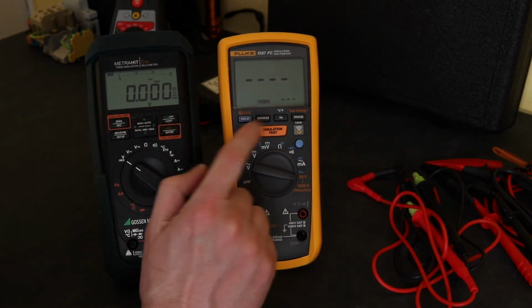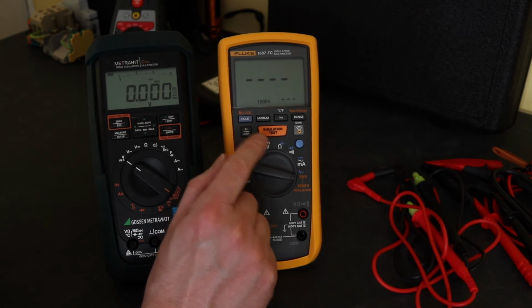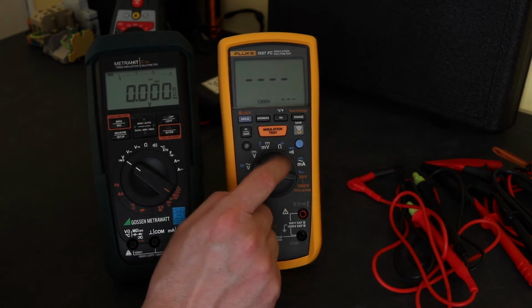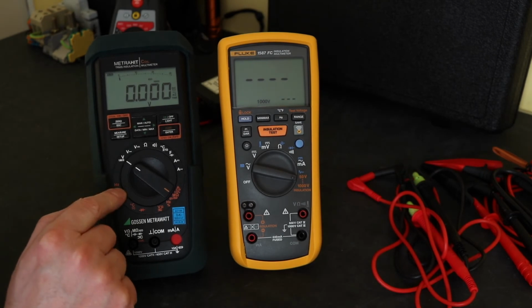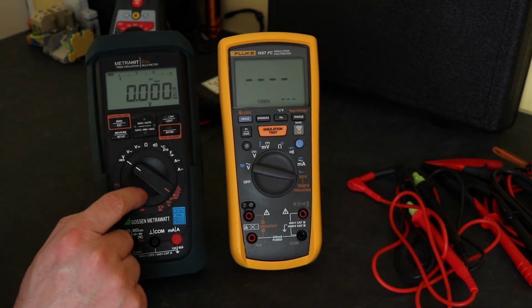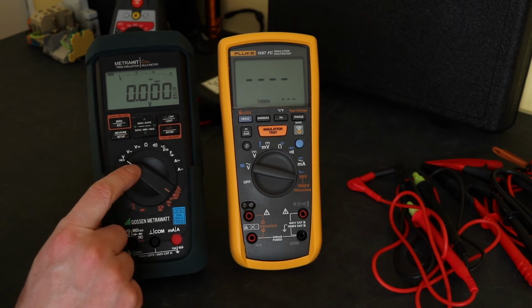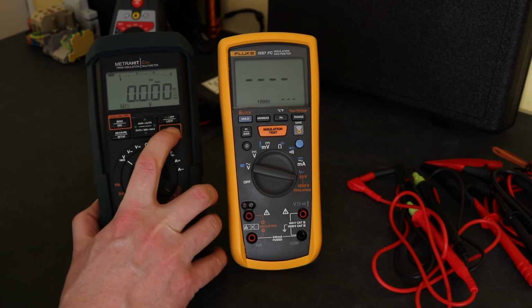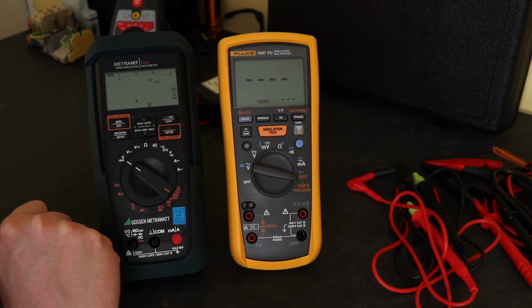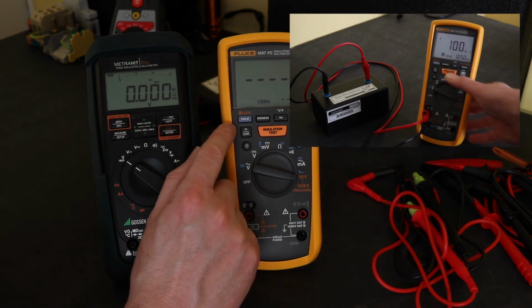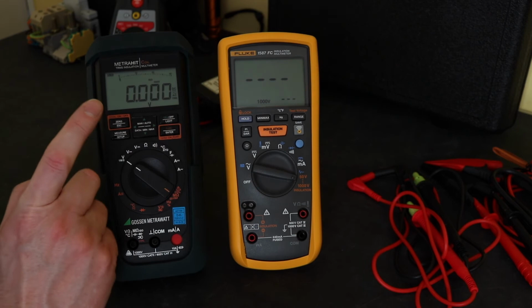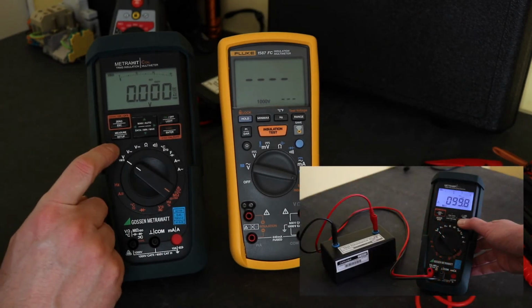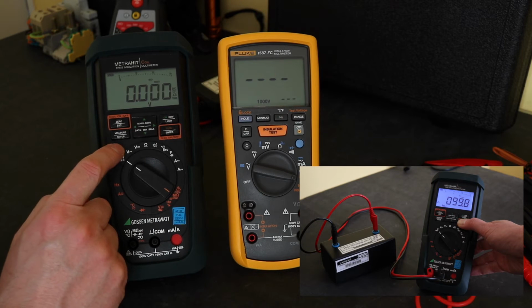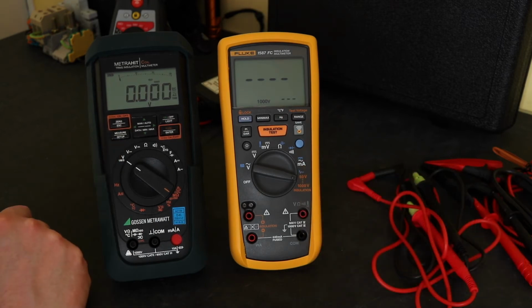We have DAR and PI ratios on this, and also time, so you can actually lock this on. The MetraHit does not have DAR and PI ratios, and there is no way to actually lock the insulation test on. You literally have to keep your finger on the button for as long as the test you want, and then let it go. What this instrument does as well, whereas these instruments will actually display the value of the insulation resistance at the end of the test when you let the button go, this flicks straight back to voltage, so you lose it, which isn't a very nice, helpful feature really. I'd much rather the insulation value stayed on the screen for you to write down.